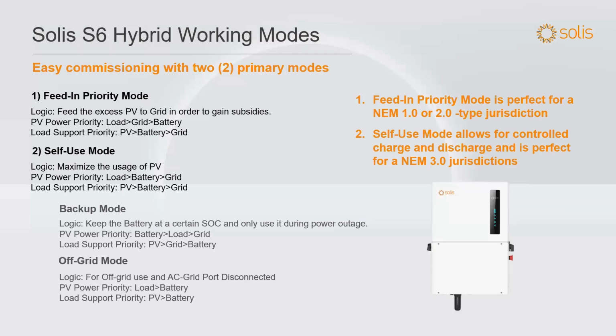You might go into what we call backup mode here and adjust your battery so that it charges up all day long and discharges from 4 to 8 p.m. When you go into your system, you do the same as grid tie commissioning: set the time and date and standard, turn on AFCI, make sure the inverter is set for 100% output, and then choose one of the primary modes. Depending on your jurisdiction, a lot of folks use this self-use mode, where you're controlling how you charge and discharge that battery, making fine adjustments in backup mode.